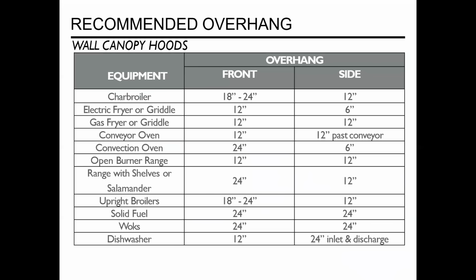Another thing we talked about was overhang, side overhang and front overhang. Code requires minimally that you have 6 inches of overhang. And the way the code is written now, you're not getting a penalty. The way the code used to be written in IMC, you took the total area, so if you made a deeper hood, you were being penalized by the exhaust rates that you would have to use. Now, the way the code reads, it's CFM per linear foot of hood. So we want to make those hoods deeper.